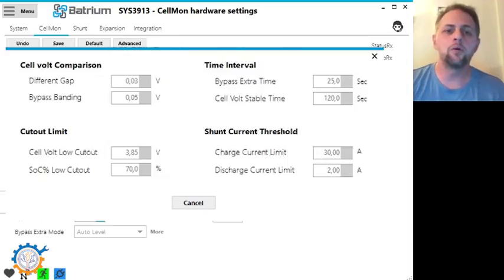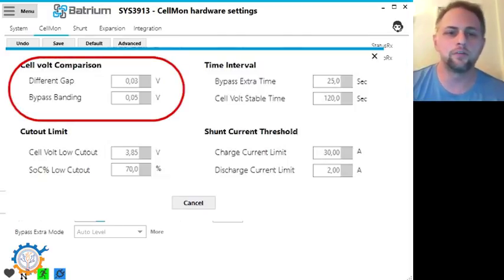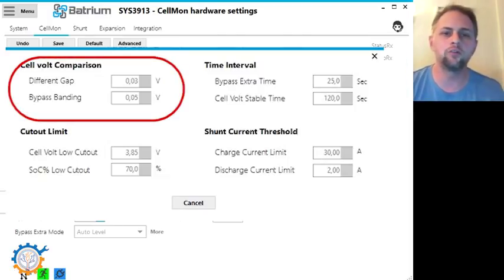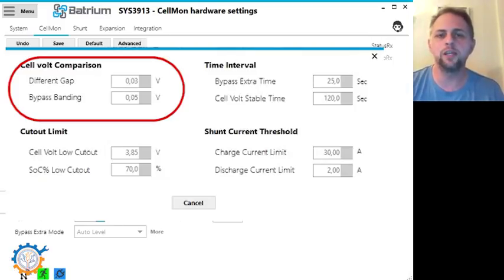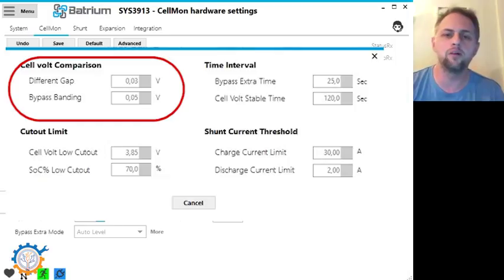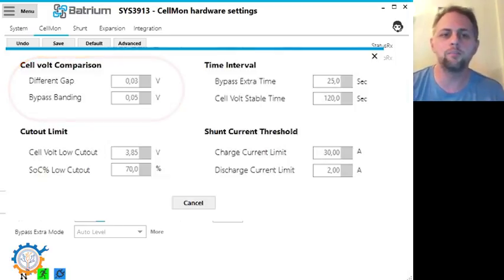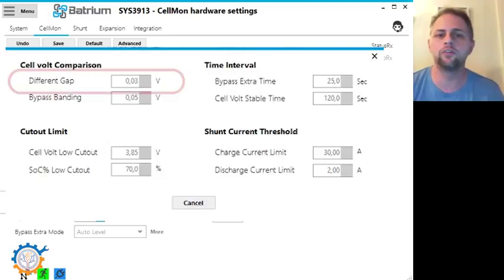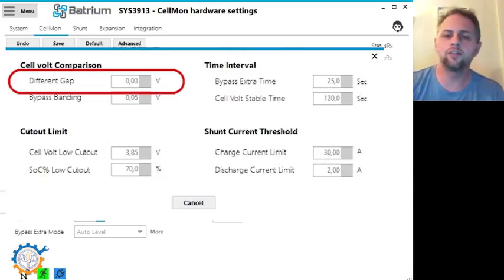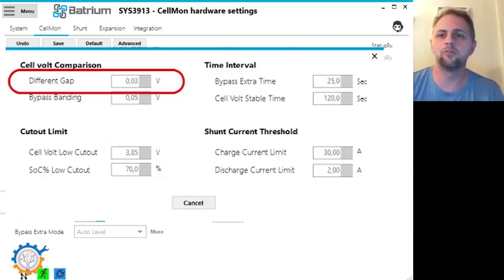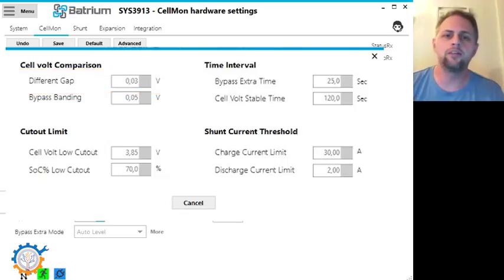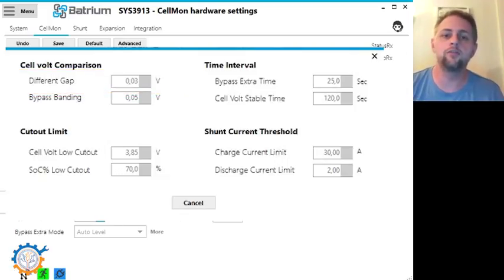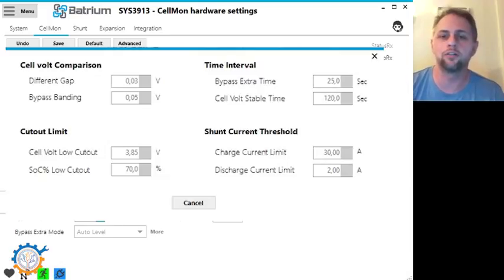Next part is the cell volt comparison and this is also very important. For instance, the different gap is the gap between the maximum and the minimum cell. If that is above in my case 0.03 volt, that sets the state of the bypass to be able to go to the next level. Everything on this screen or in this window here needs to be true in a sense for the bypass to actually start.